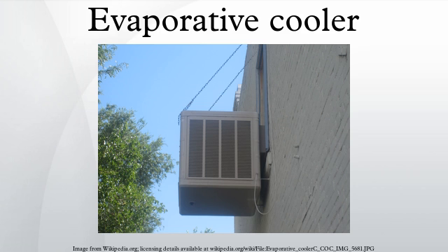Physical principles. Evaporative coolers lower the temperature of air using the principle of evaporative cooling, unlike typical air conditioning systems, which use vapor compression refrigeration or absorption refrigeration. Evaporative cooling is the addition of water vapor into air, which causes a lowering of the temperature of the air. The energy needed to evaporate the water is taken from the air in the form of sensible heat, which affects the temperature of the air, and converted into latent heat, the energy present in the water vapor component of the air, whilst the air remains at a constant enthalpy value.